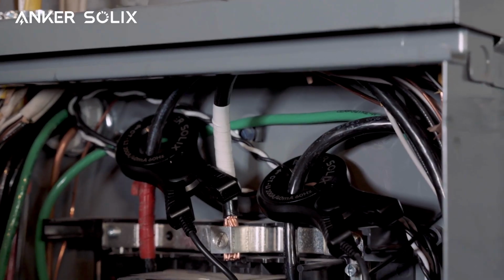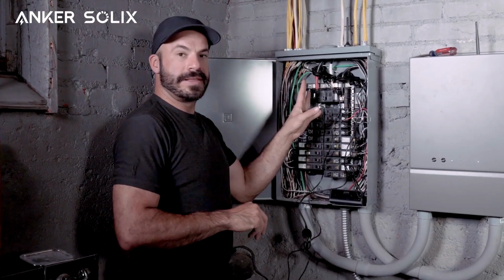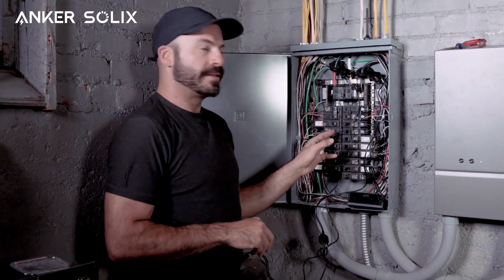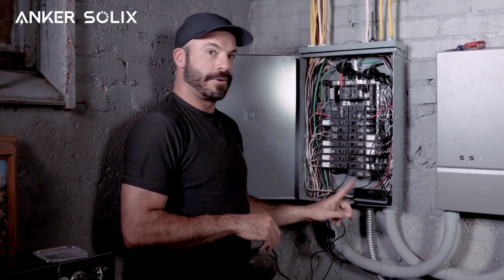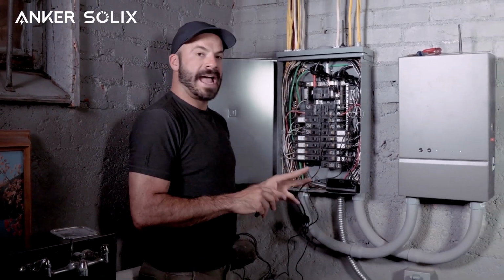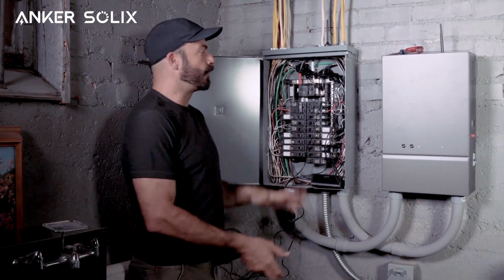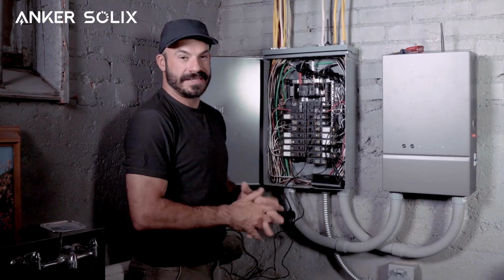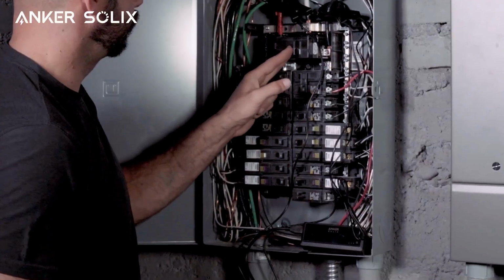Now that we have all these connections complete, we're going to power everything back on, the main breaker and the two branch circuit breakers that supply power to the smart meter. We'll connect it to the app and verify everything's working before powering everything off and proceeding to the next step, which is installing the bidirectional inlet box.